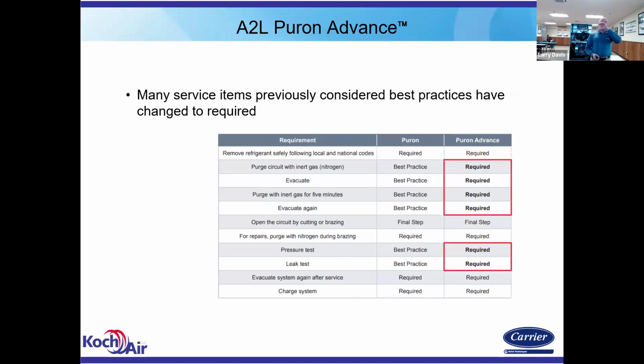Again, this is a nice quick chart that shows a comparison in service best practices between Puron and the Puron Advance. When you're removing a component, you have to remove the refrigerant, still have to recover it, nothing changed there. But this is where you have to do the double evacuation and purge. Where that was a best practice before, a recommendation before, you have to do it now. Okay. Then you open the circuit.